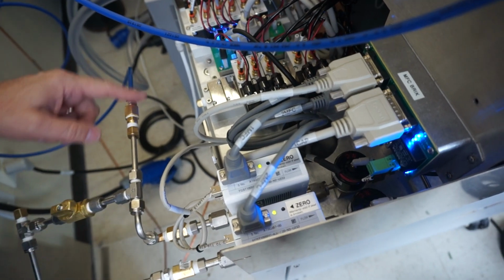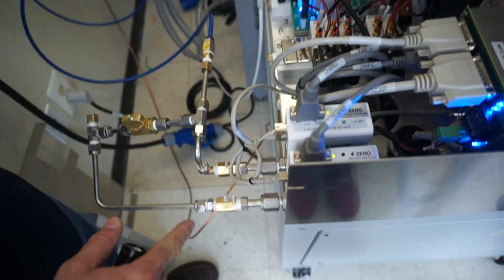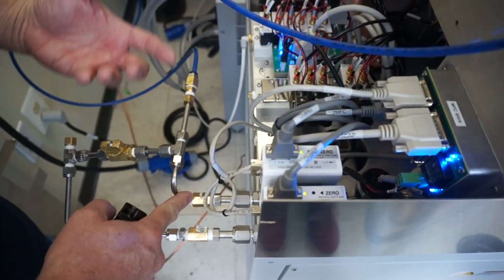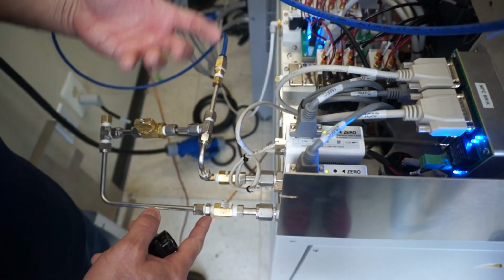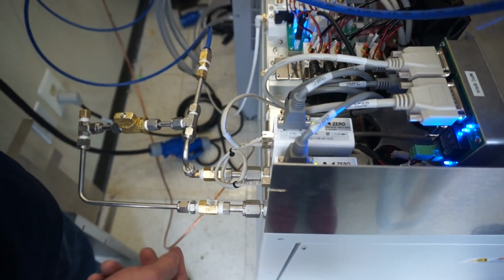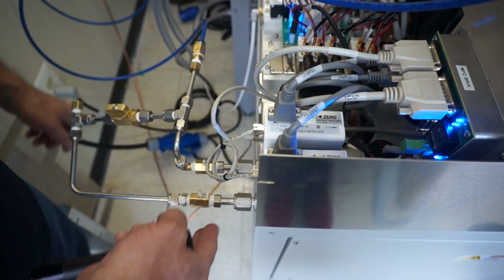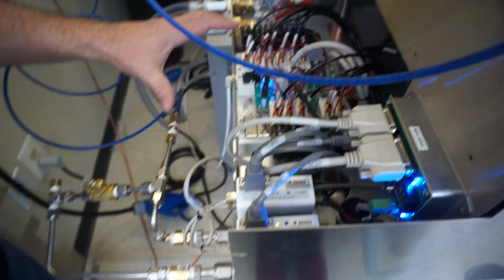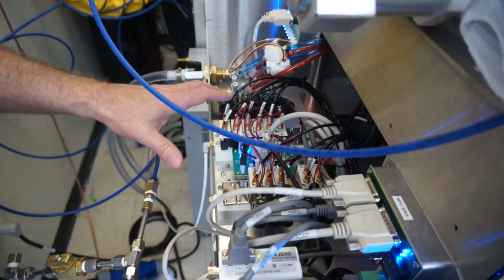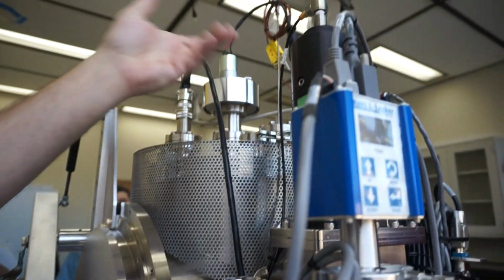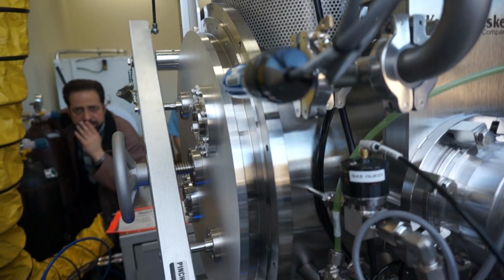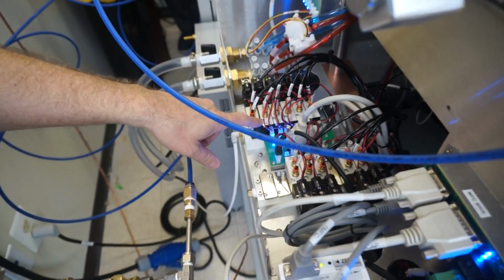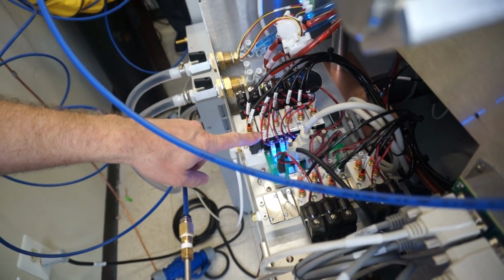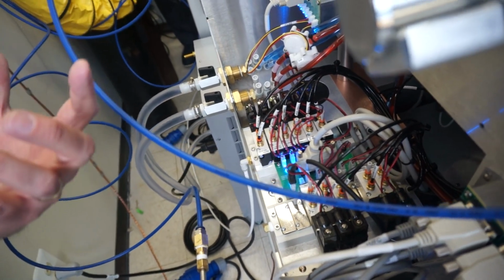So right now you have everything hooked up into argon, but in the past you have argon going to mass flow controller 1, and whatever your nitride or oxide, whatever gas you want to have going into the second one. Also within here are some pneumatic solenoids. So you'll notice on this tool there's a lot of this, I think it's this 4mm black tubing. The tool basically runs off of compressed air. You go through a solenoid block. The solenoid block is mapped to the output of the controller, to what signal we want to use.